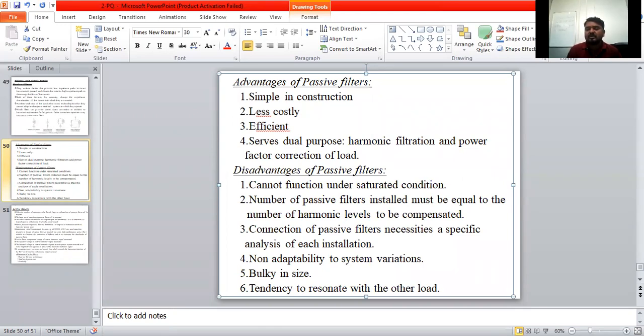Now, what are the drawbacks of passive filters? The number of branches is more because of the different harmonic levels. With active filters we can use only one filter for all the different orders. Because of that we can reduce the cost, the branches, the design, and the large size and large devices; we can use reduced devices. So we get low cost and high performance, suitable for eliminating harmonics of different orders. By using active filters, we can solve the drawbacks of passive filters.